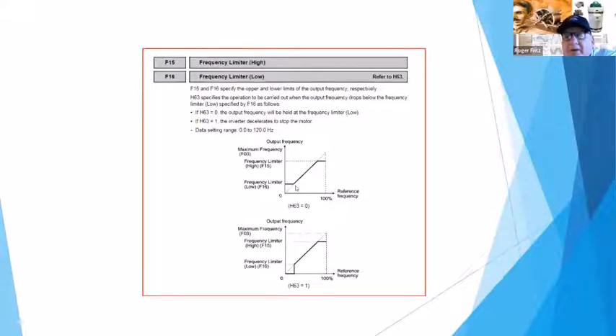So if you have a pump and you're not pumping water until 30 hertz, you don't want to ever allow the customer or the people to run that too slow, or the pump will go into cavitation. There also are multiple other parameters.